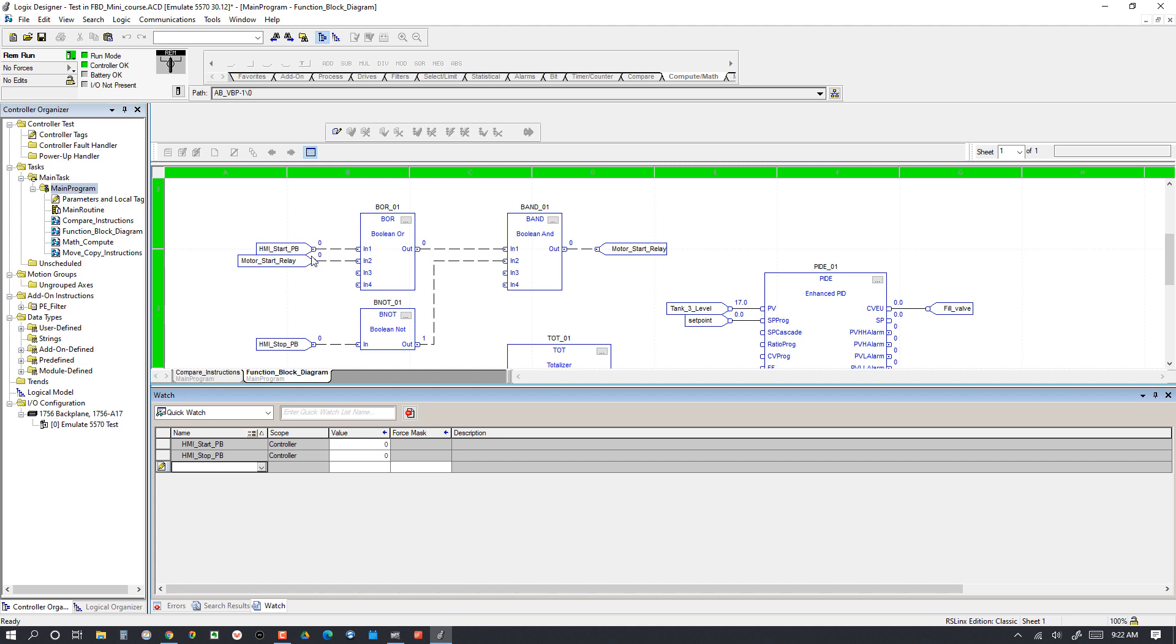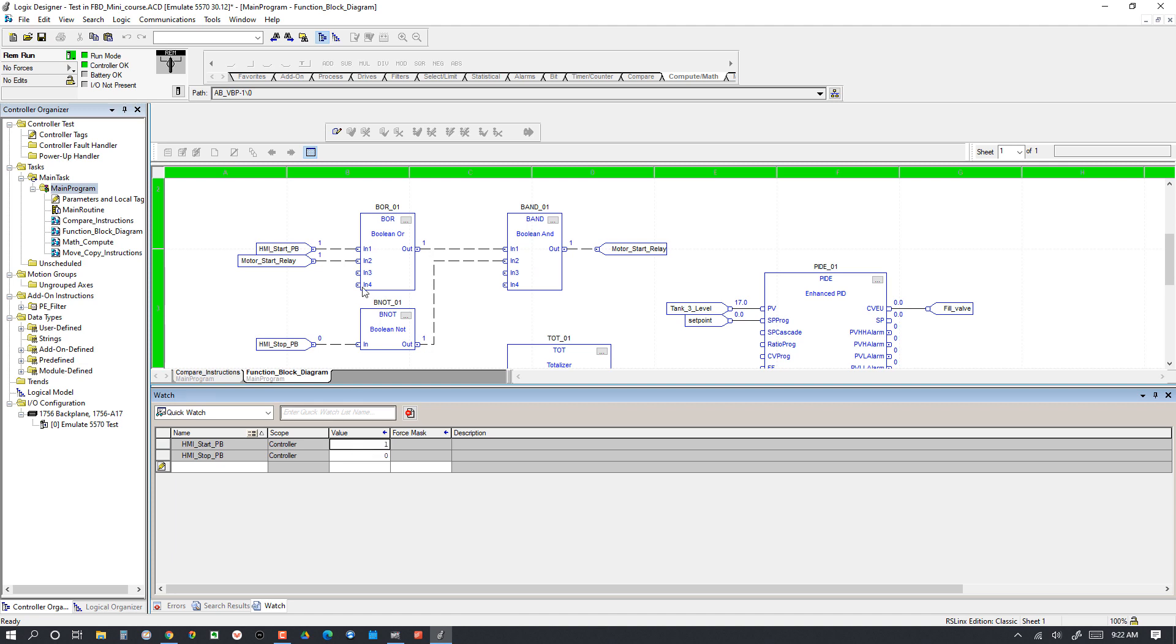What we expect to happen is that when we push the start button it is going to latch in the start relay, and then once the start relay is on it is going to latch this in and stay on even when the start push button is released. Let's try it out. We will turn this to a 1 which makes HMI start PB 1, makes the output 1, makes this a 1, which then makes this a 1. Then when we release the push button it will go back to 0.